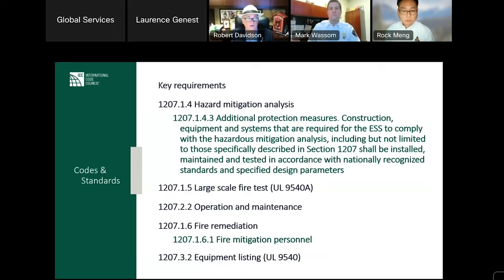That's not in 1207. No, both fire codes typically have requirements for hydrants and fire flow, because the fire department needs water once they respond. So, you have to comply with NFPA 72 for the installed protection systems, and you have to comply with all the details of NFPA 69 if you're doing a concentration reduction system, right? So there's a lot of other parts of the building codes and other reference standards that all come into play, and those documents are supposed to be coming in also. The large-scale fire test is critical to understand what size the event can be and what's going to be controlled in the event of a catastrophic failure.